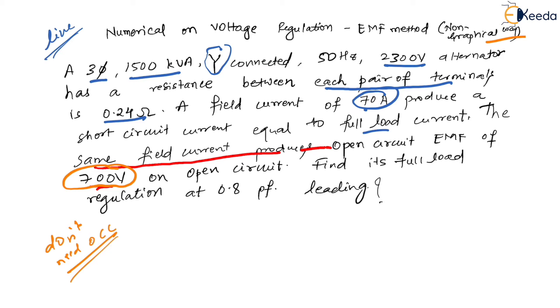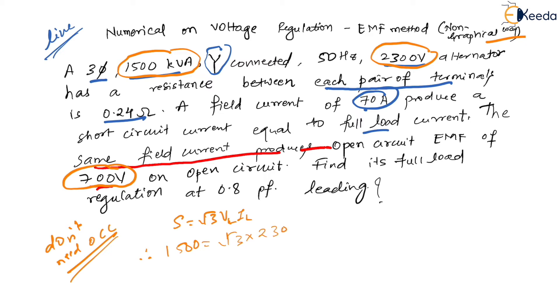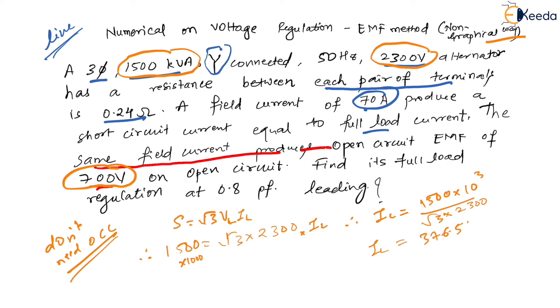Now, 1500 kVA is given, and the voltage is 2300 volts. To find the rated current, we use S = √3 × VL × IL. So 1500 × 10³ = √3 × 2300 × IL. Solving this gives IL = 1500 × 10³ divided by (√3 × 2300), which equals 376.5 amperes.